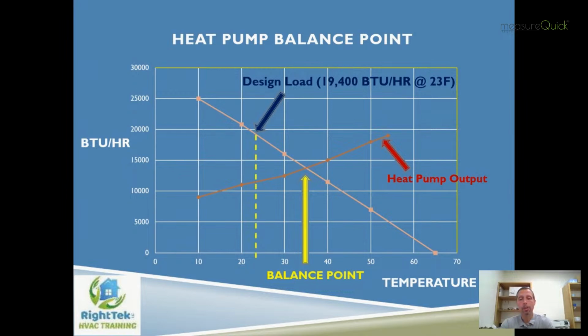So if you look to the left of my thermal balance point, as I head towards 23 degrees, you're going to notice there's a gap forming there. There's a triangle forming. That's the point where, if I use the old method or the current simplified method, I've got to make up that amount of heat somehow. That's what we need auxiliary or supplemental heat for. So if we're going to design a system that still includes some form of supplemental heat, this allows me to see what that need is.